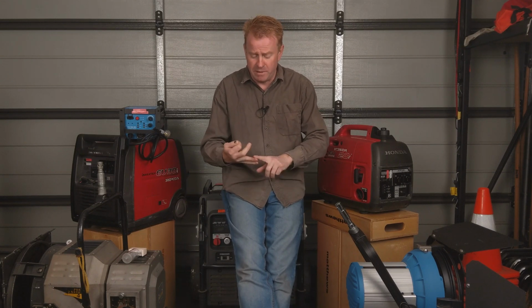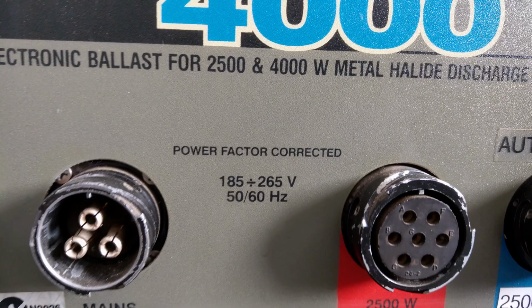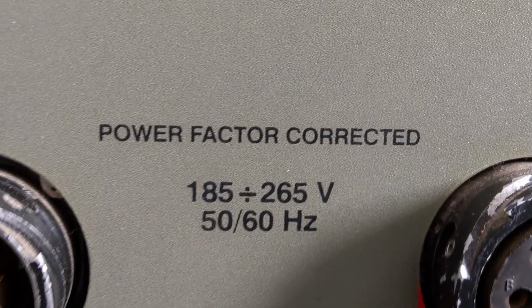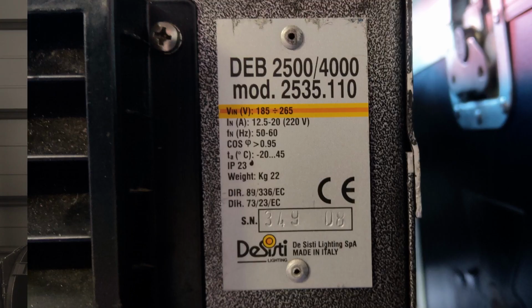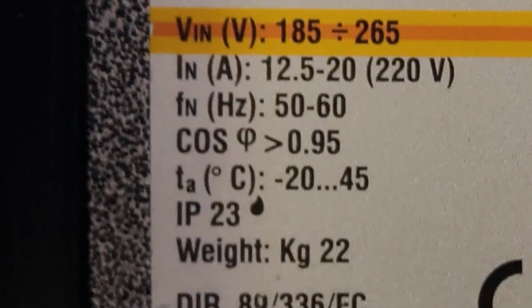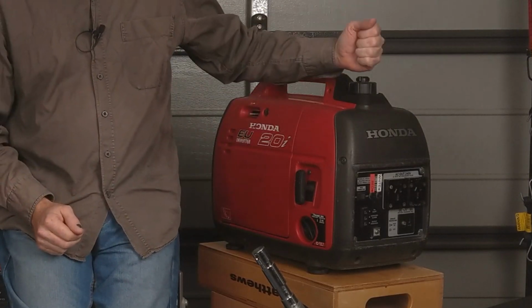All right, so how do you tell if your ballast is power factor corrected or not? Well, here's the interesting thing. It doesn't matter if it's a big brand name. It doesn't matter if it's electronic. It doesn't matter if it's compact. It doesn't matter if it's got 1000 hertz mode. You can have all of these things and still have a ballast that is not power factor corrected. So how do you tell? Okay, well, some ballasts actually have it written on them. And ballasts that have a compliancy plate, if you have a read of the compliancy plate and you look for a cosine phi symbol, that tells you the power factor rating. So what you're looking for is something above 90, ideally 95 and higher. Now, if that rating is below 90, I wouldn't bother trying to run it off a portable generator.